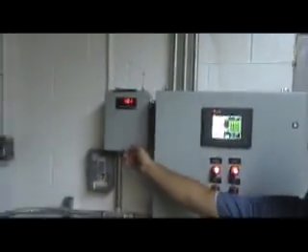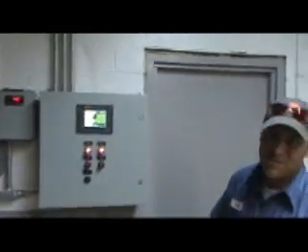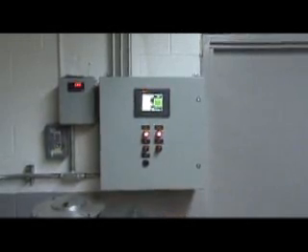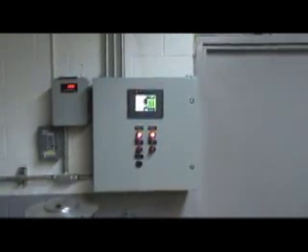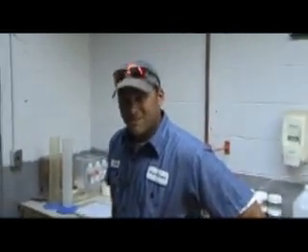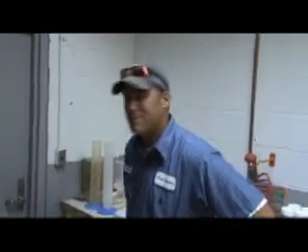Let's take a look in here. This is the control that runs them, off the DO probe up in the tanks. This controls the VFDs. On DO, you don't even have to do anything — the blowers will adjust up and down. I can hear the rotation going up and down. It saves energy. That's the big thing.